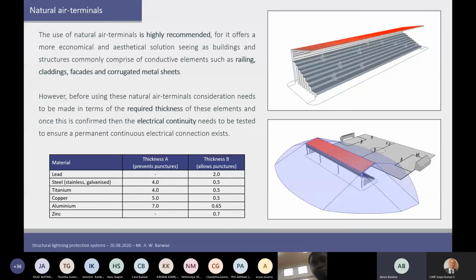Earlier on, I stated that we have to be cognizant of the costs. So what we look at when we are dealing with lightning protection systems in such areas is that we want to find natural elements, so naturally conductive elements. Here's an example of a soccer field with a small pavilion. The pavilion is made up of a steel roof, like an IBR sheeted roof. We have steel I-beams coming down, and maybe even it's either concrete or steel here where the surface is where people are sitting.